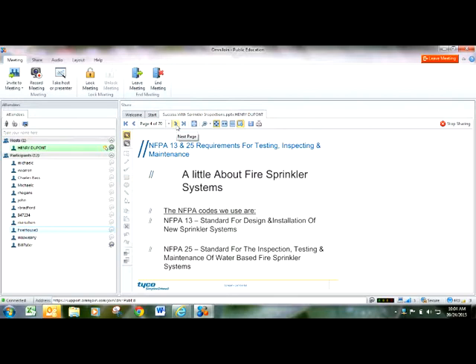So basically, there's two standards when it comes to fire sprinkler systems that we use. The first standard is the most common standard, NFPA 13. The other is NFPA 25. NFPA 13 goes over how you design sprinkler systems, what's allowed, the components, what are required, hydraulic calculations, and so forth. NFPA 25 is the other standard, and it's kind of the wear and tear standard for sprinkler systems. The intent of NFPA 25 is not to tell you how to design a system or to even check to make sure that the system is designed correctly. It is there just to check to make sure that components of the sprinkler system are functioning the way they're supposed to be functioning. That's why they call it the wear and tear standard.